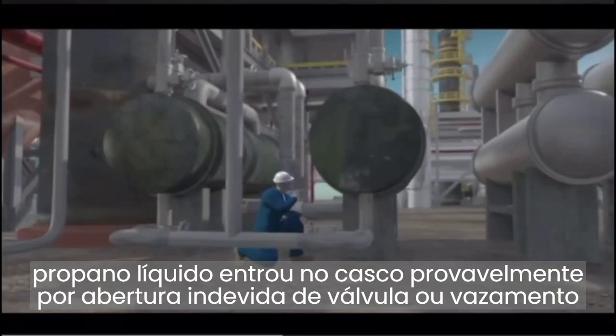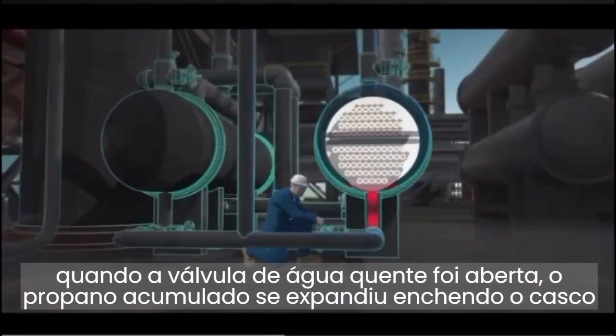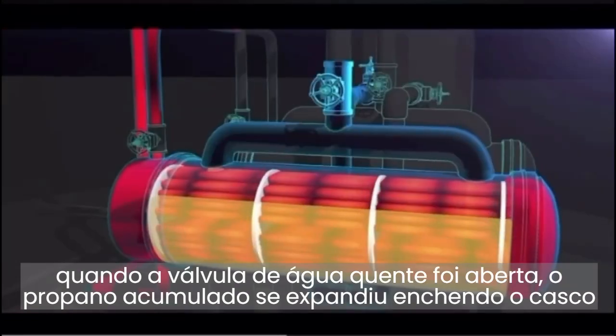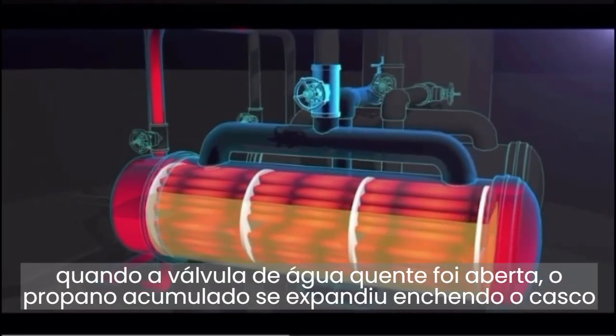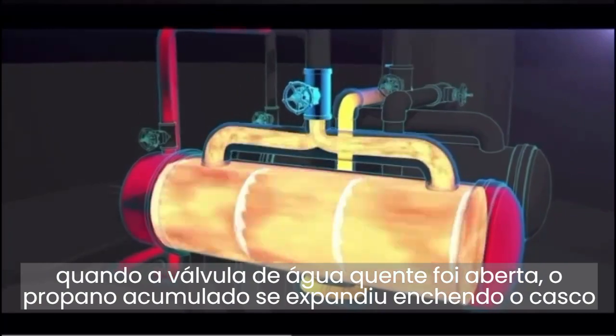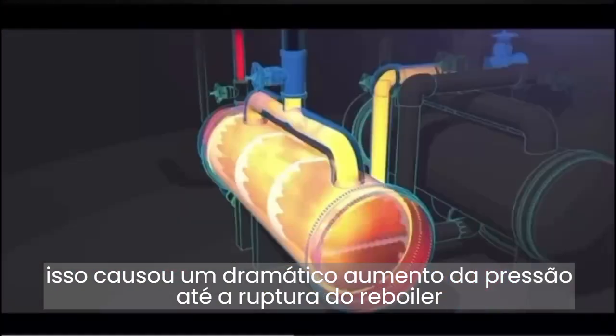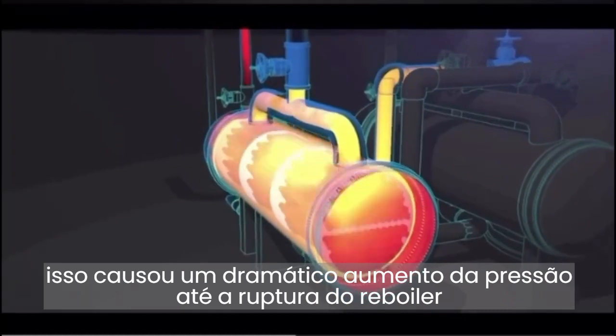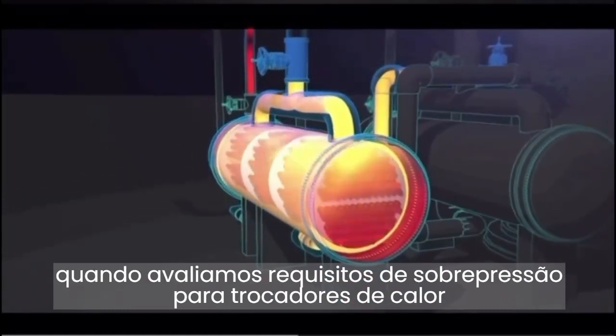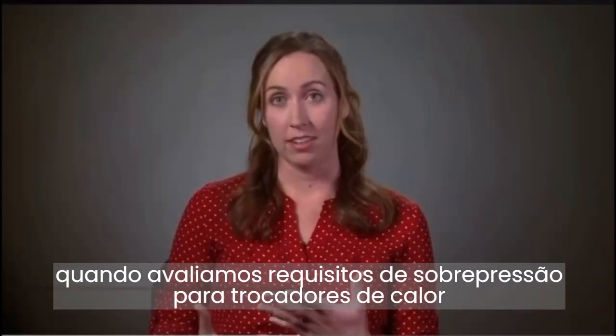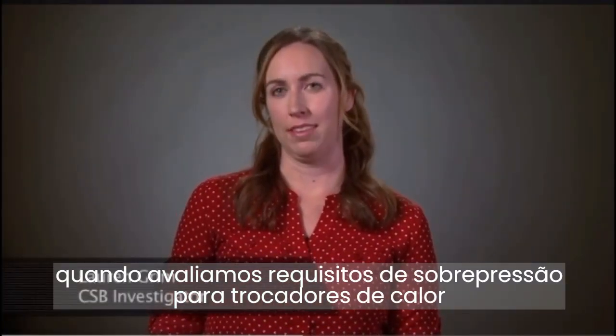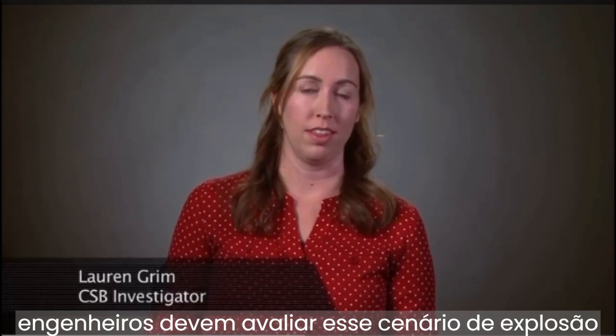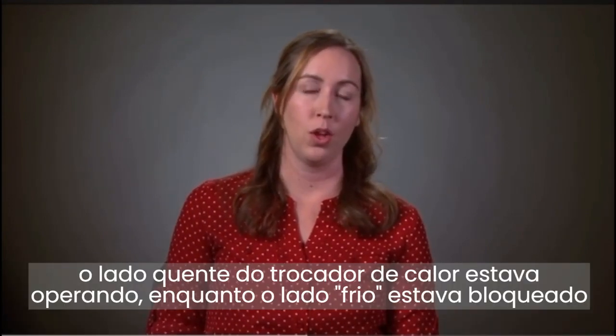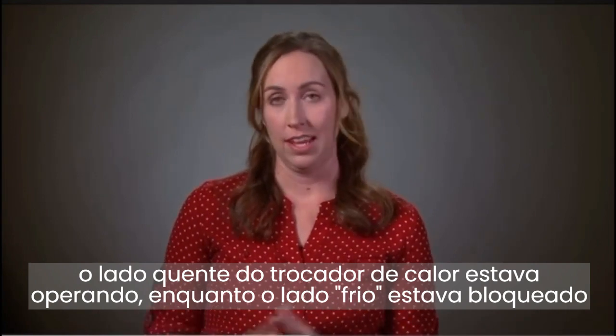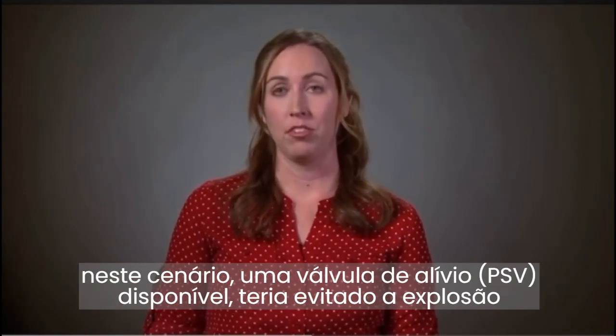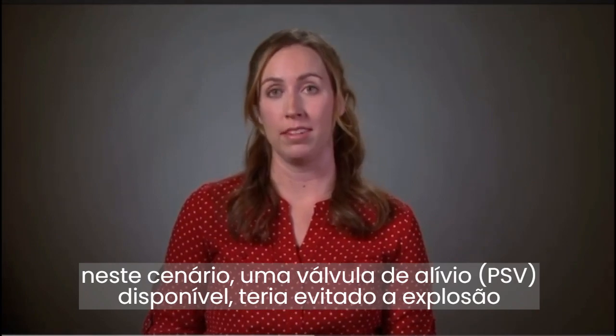The CSB determined that when the operations supervisor opened the hot water valves to the standby reboiler, the propane liquid trapped inside was heated and expanded in volume to completely fill the reboiler shell. This caused pressure to dramatically increase until the reboiler ruptured. When identifying overpressure protection requirements for heat exchangers, engineers should evaluate the scenario that caused the Williams explosion. The hot side of the heat exchanger was operated while the cold side was blocked in. In this scenario, just having a pressure relief valve available could have prevented the explosion.